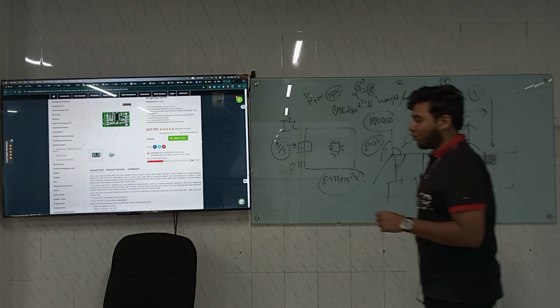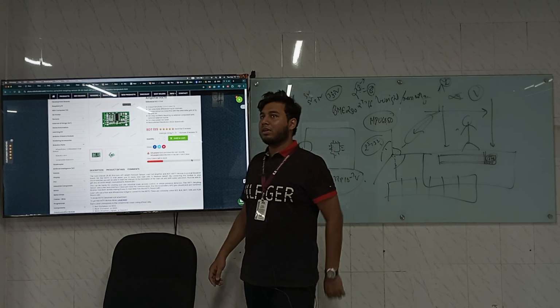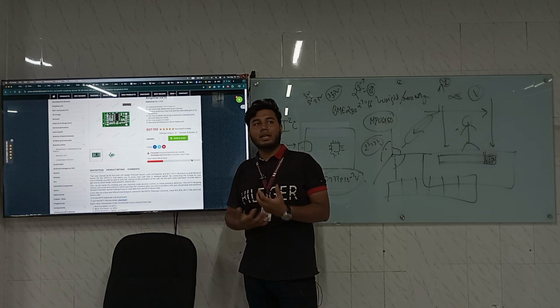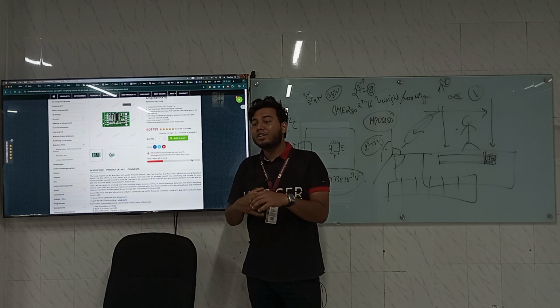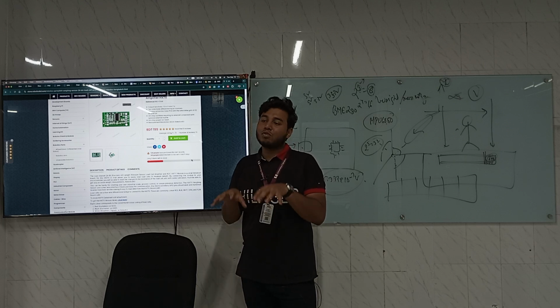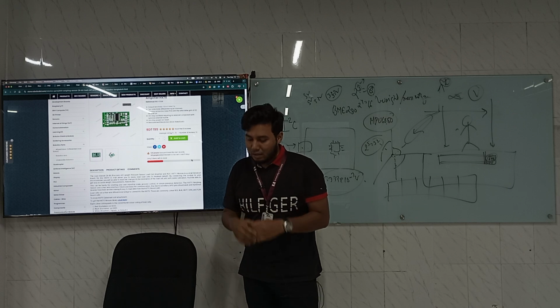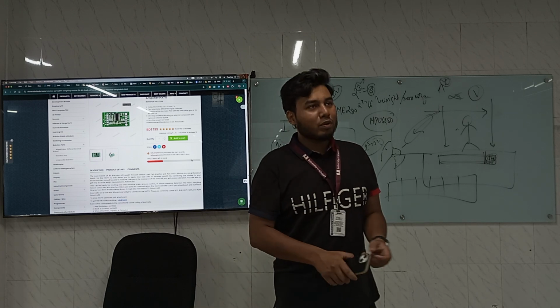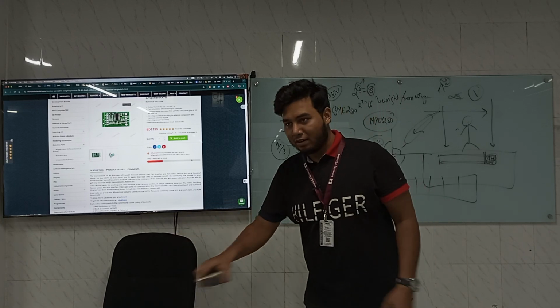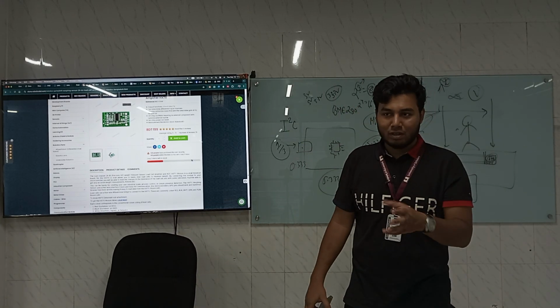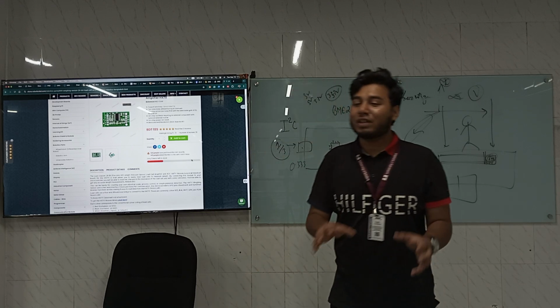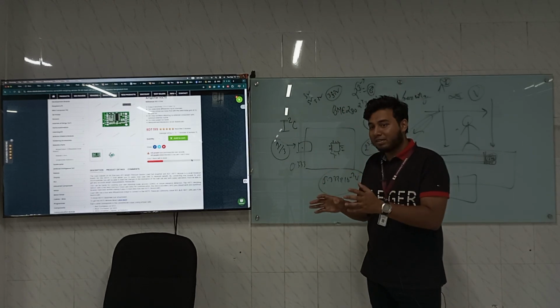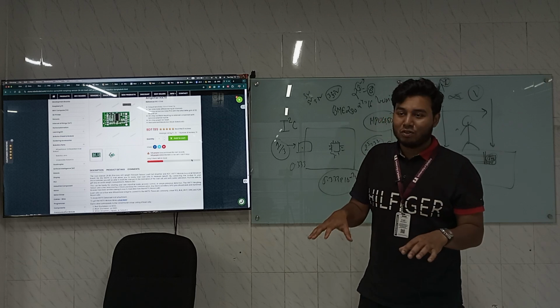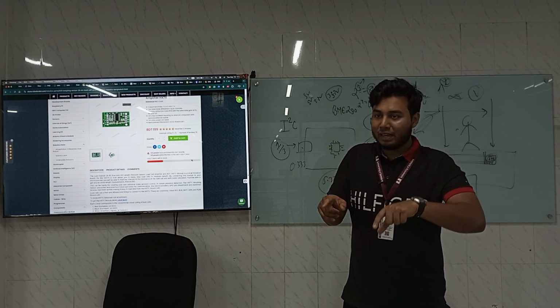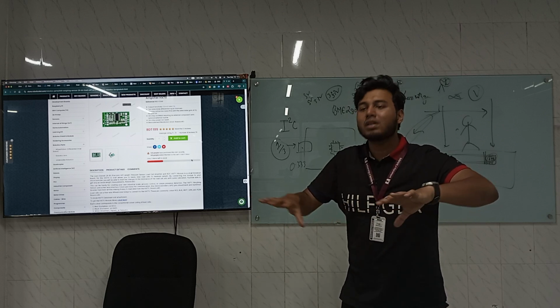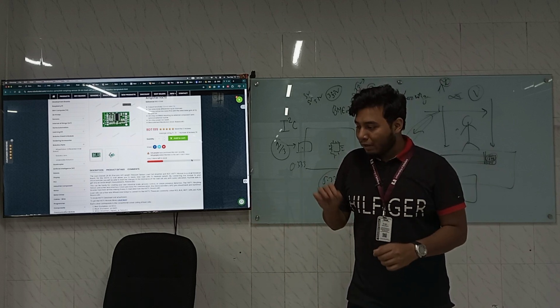What is the meaning of calibration? Whenever you are working with a new device in a new environment, you have to set it to a null point. It won't work properly if you just put your phone on the load cell and expect a correct value — you first have to make it understand that it's zero right now. Once you've set it to totally zero, with no weight on it, then you can put the object on.